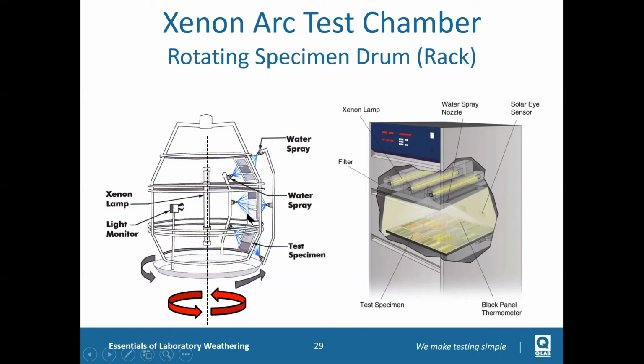So let's check the rotating drum model. If the customer only puts the specimen in the middle layer, that sounds like it's pretty uniform, right? Because the distance from the specimen to the lamp is exactly the same. But the problem is it's not a single layer. There are 3 layers. So here and here, the sunlight has a different angle and different distance. It's a little bit different. And the big part is about the water. See, if the water sprays onto these 3 panels, the water will go down to here. So the water delivery in the rotating drum tester is not uniform at all.